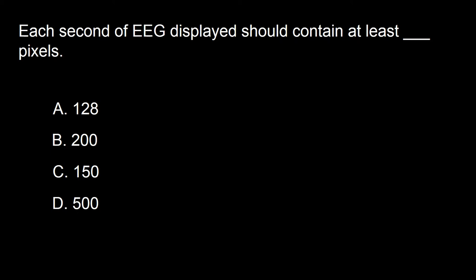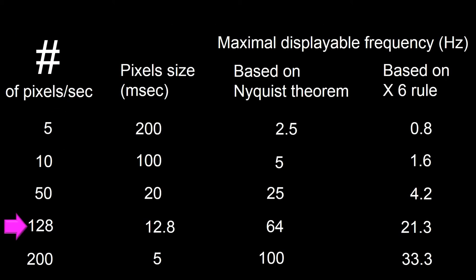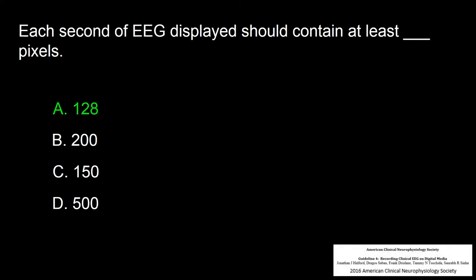Next question: each second of EEG displayed should contain at least dash pixels. A: 128, B: 200, C: 150, D: 500. The answer is 128 pixels per second, which gives a pixel size of 12.8 milliseconds and a maximal displayable frequency of 64 Hz. The answer is A.